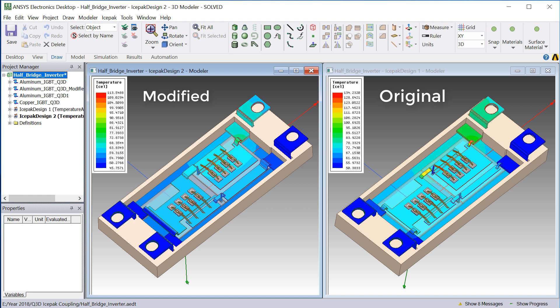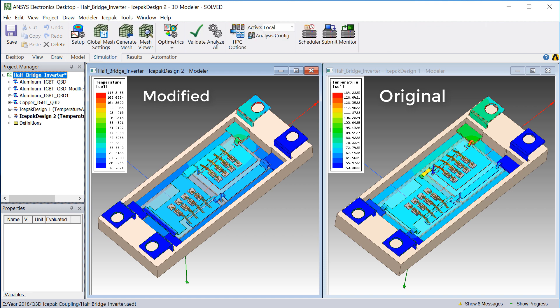Therefore, the modified design has 20.5 degrees more safety margin before it can overheat and damage the IGBTs. This should improve the reliability significantly at high ambient temperatures.